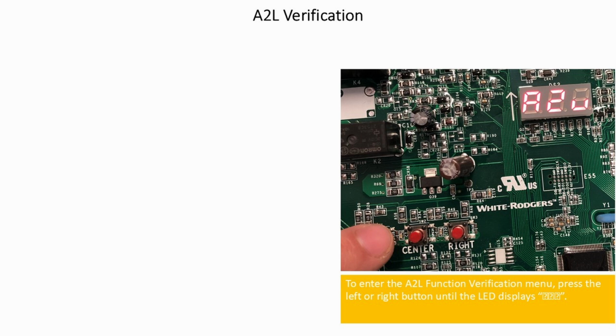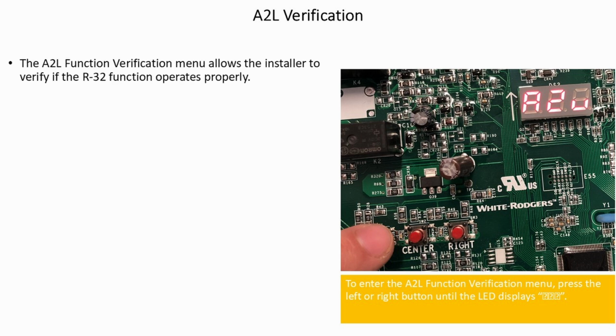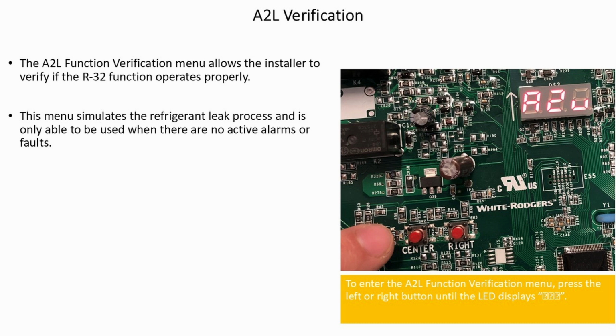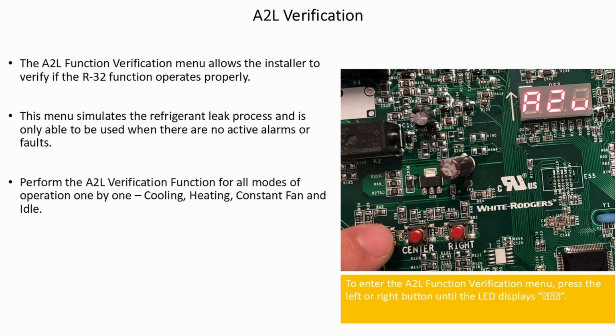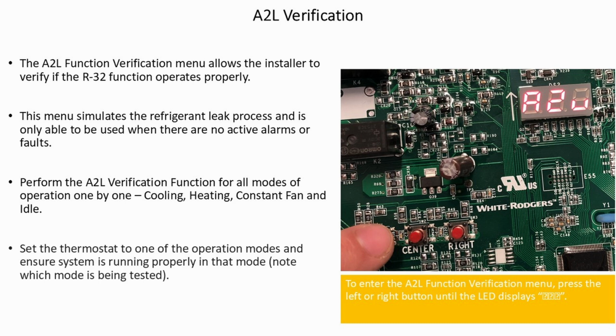A2L verification. The A2L function verification menu allows the installer to verify if the A2L function operates properly. This menu simulates the refrigerant leak process and is only able to be used when there are no active alarms or faults. Perform the A2L verification function for all modes of operation one by one: cooling, heating, constant fan, and idle. Set the thermostat to one of the operation modes and ensure the system is running properly in that mode. Note which mode is being tested.